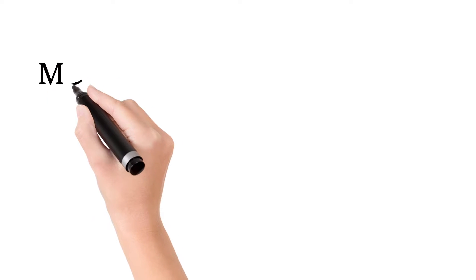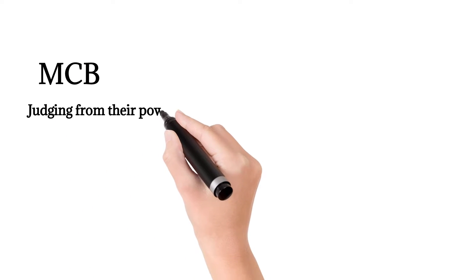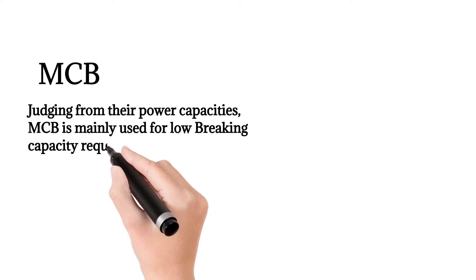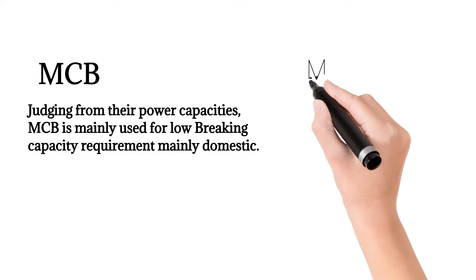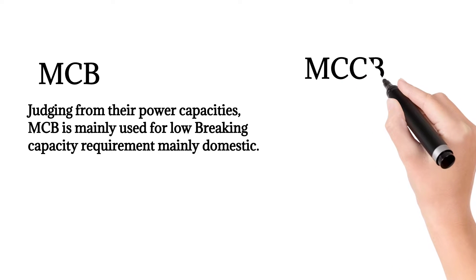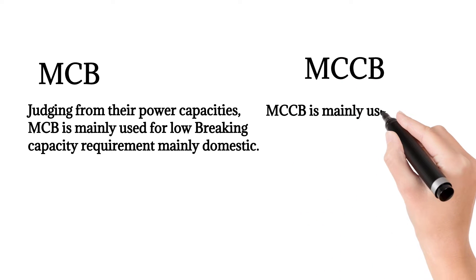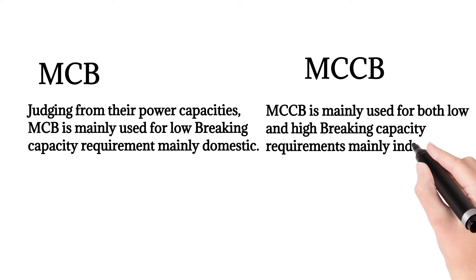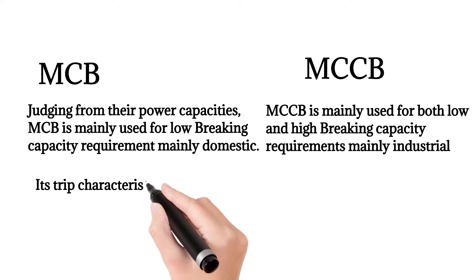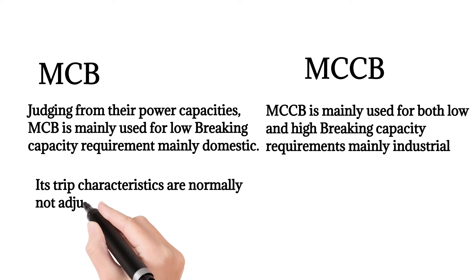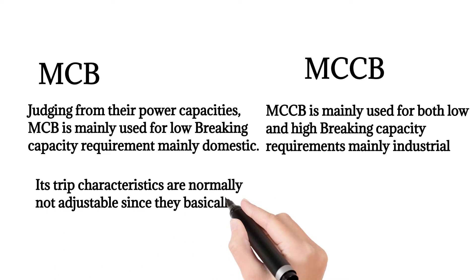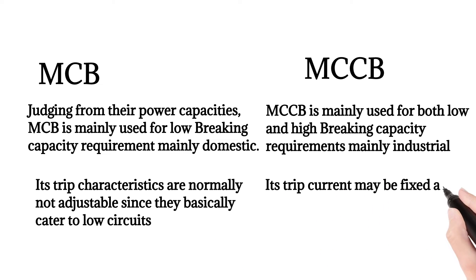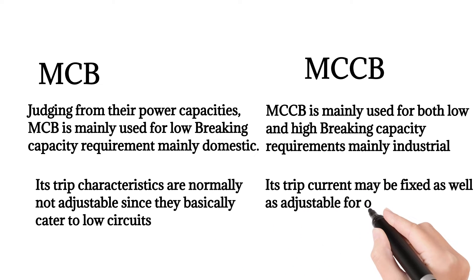Judging from their power capacities, MCB is mainly used for low breaking capacity requirements, mainly domestic. MCCB is mainly used for both low and high breaking capacity requirements, mainly industrial. MCB trip characteristics are normally not adjustable since they basically cater to low current circuits. For MCCB, its trip current may be fixed as well as adjustable for both overload and magnetic settings.